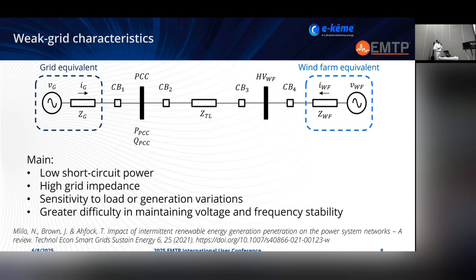So at this point of interconnection, normally point of common coupling, we have some main characteristics that a weak grid defines. So the main components are a low short circuit power, a high grid impedance, and since we have these two components, we can have some variations or load variations, and this can increase the sensitivity at this point. It can also be very difficult to maintain voltage and frequency stability at this point of common coupling.